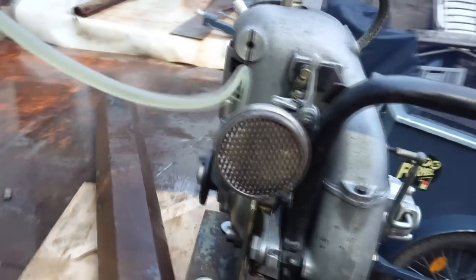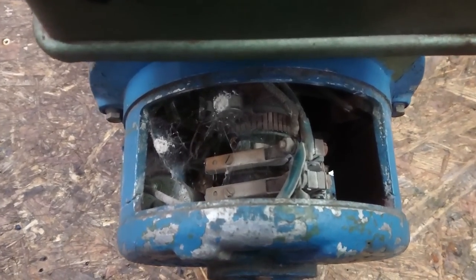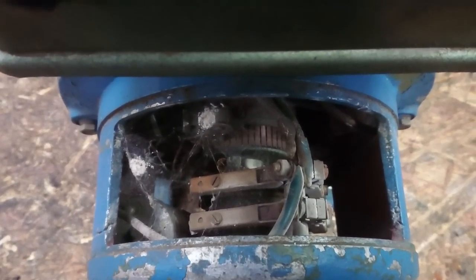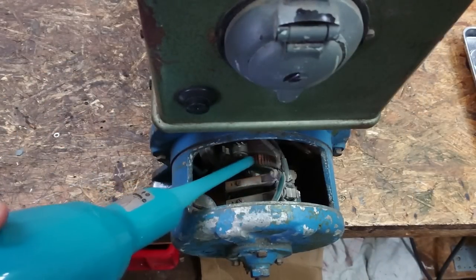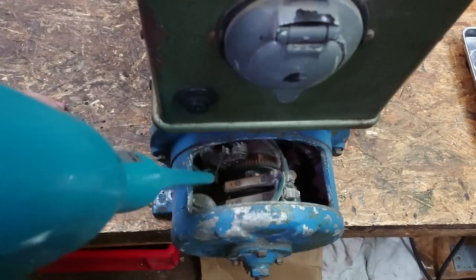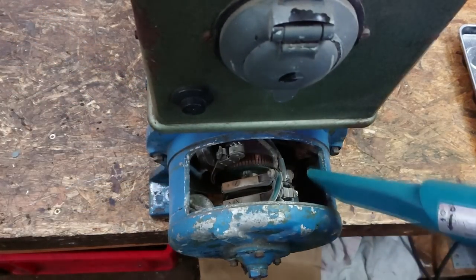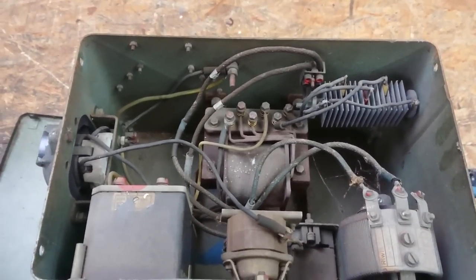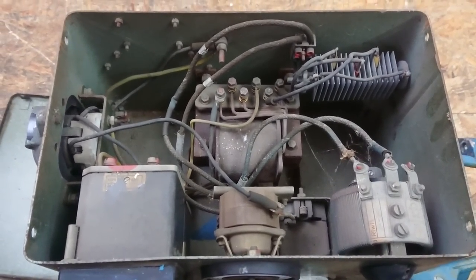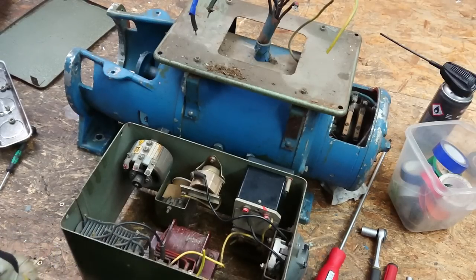These engines don't like being operated without a load, so let's continue with the repairs. Getting the engine running is only half the job with these generators — we have to check the synchronous generator and look inside the enclosure as well. Here we see the brushes of the slip rings and of an additional commutator. We'll talk about why the generator has both in just a minute. Inside the enclosure we find a number of electric components, all of which are really dusty. In order to clean and inspect everything, I disconnect the entire unit temporarily. Other than the dirt, I can't see any obvious problems.